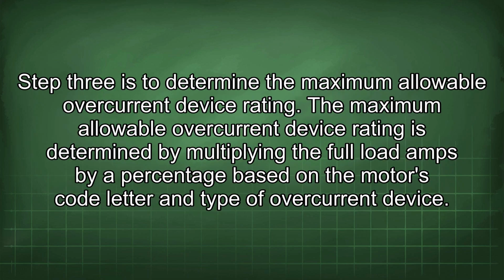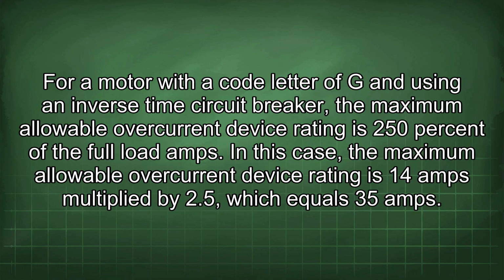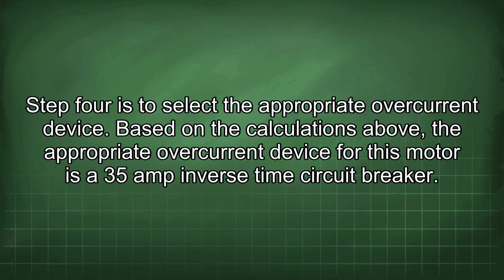Step 3 is to determine the maximum allowable overcurrent device rating. The maximum allowable overcurrent device rating is determined by multiplying the full load amps by a percentage based on the motor's code letter and type of overcurrent device. For a motor with a code letter of G and using an inverse time circuit breaker, the maximum allowable overcurrent device rating is 250% of the full load amps. In this case, the maximum allowable overcurrent device rating is 14 amps multiplied by 2.5, which equals 35 amps. Step 4 is to select the appropriate overcurrent device. Based on the calculations above, the appropriate overcurrent device for this motor is a 35 amp inverse time circuit breaker.